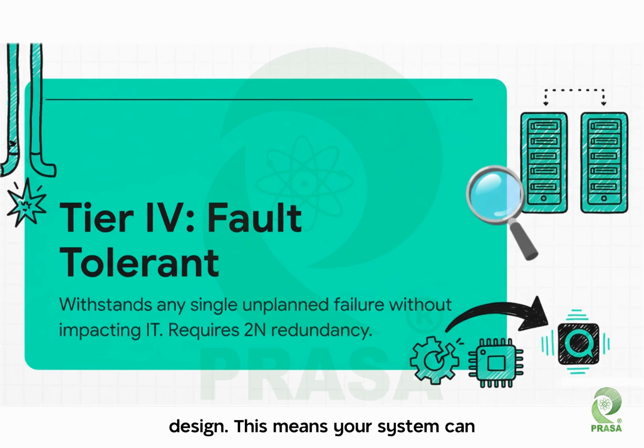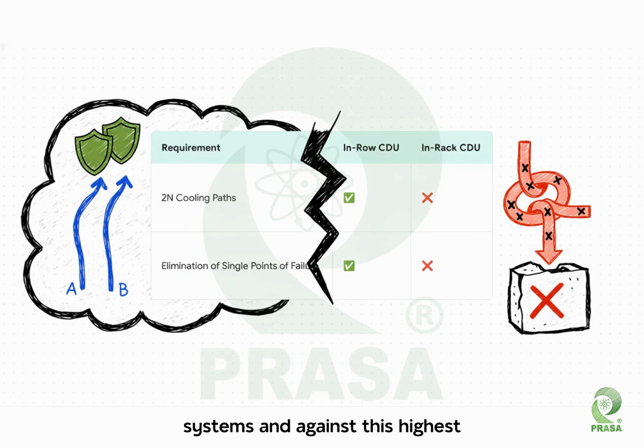This means your system can survive any single unplanned failure, a pump suddenly seizing, a controller crashing, and keep operating without a single blip. This requires full 2N, or two completely independent redundant systems. And against this highest standard, the difference becomes even more crystal clear. An in-row system can be properly designed with totally separate A and B cooling paths to achieve that 2N fault tolerance. The in-rack CDU, with all those single points of failure we talked about, it's not even in the same league. It doesn't get close.